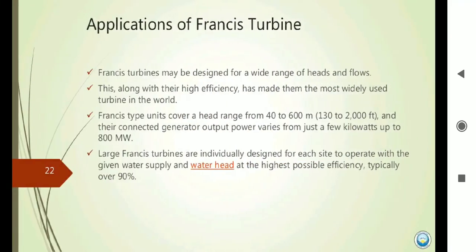The Francis Turbine is useful for a wide range of head and flow conditions. It is a medium flow reaction turbine with a medium head of 50 to 300 meters. It is designed for its specific operating conditions with the given water supply. Water efficiency is typically over 90%. It is a medium flow and medium specific speed turbine.